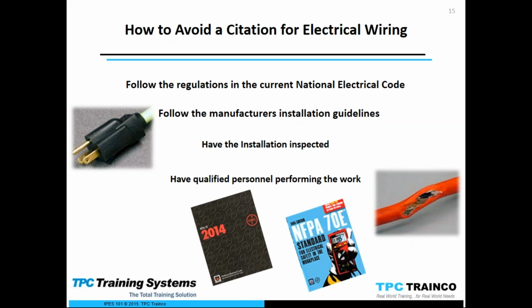OSHA wants a list of your qualified personnel. So if I were an OSHA inspector, I could walk into a facility and ask for a list of all your qualified electrical workers. I could walk up to one of those workers and ask what personal protective equipment they wear for 6 calories per centimeter squared of incident energy. If the worker could tell me, everything would be all set. If they couldn't, OSHA's probably going to dig a little deeper.